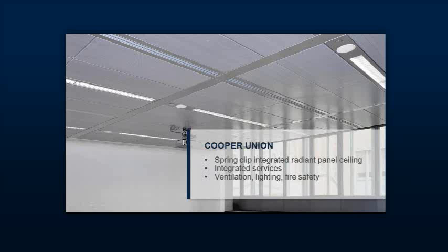So the first technology that I will briefly discuss is radiant. And the radiant that I'm going to talk about is based on water heat transfer. This is not based on electrical reheat radiant components. But even if it were, the fundamental component of radiant heat is that it is heat transfer without a media. It's all electromagnetic, so it's all line of sight.